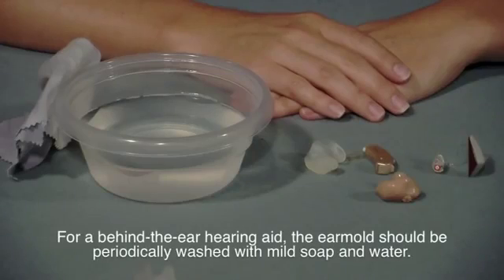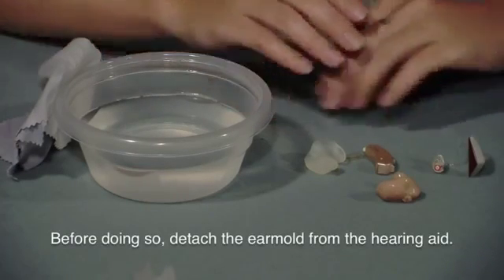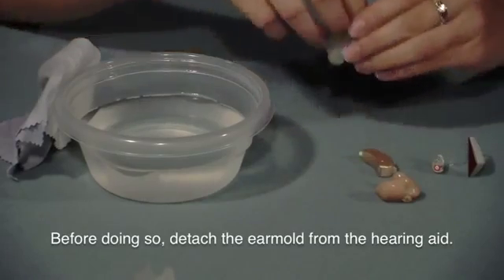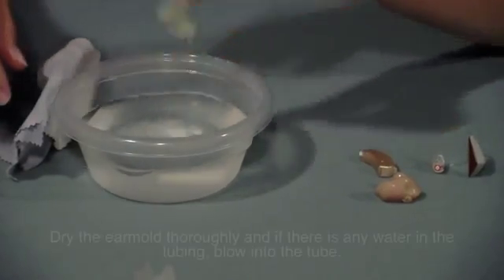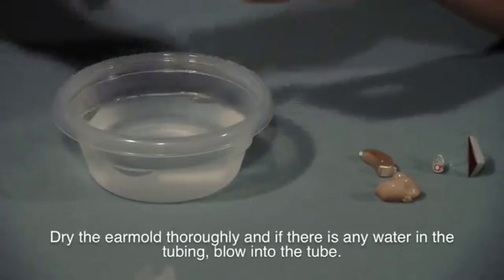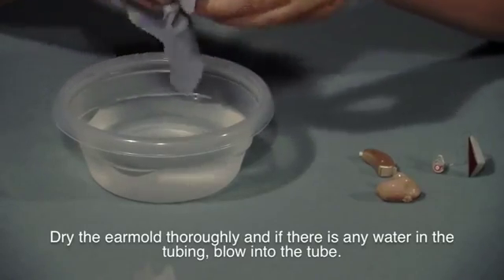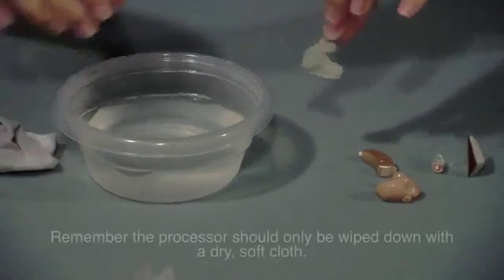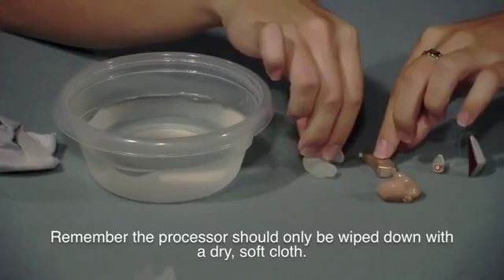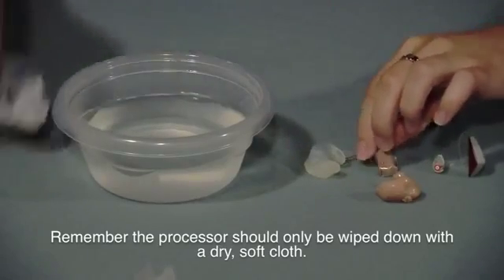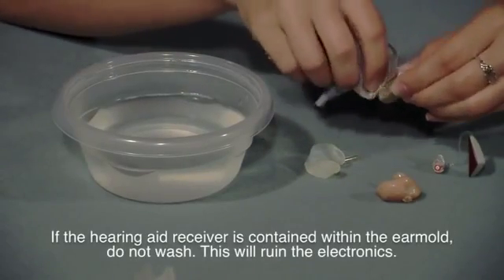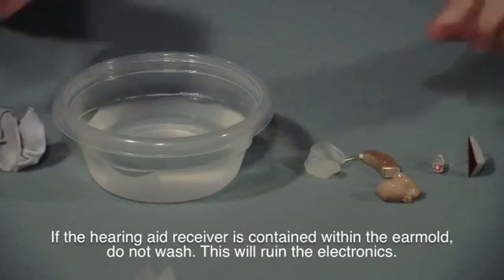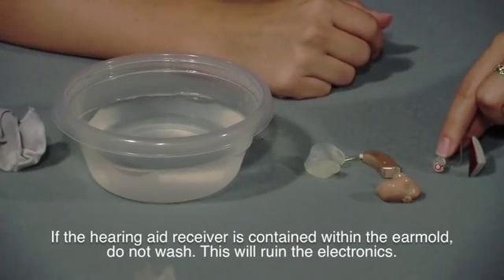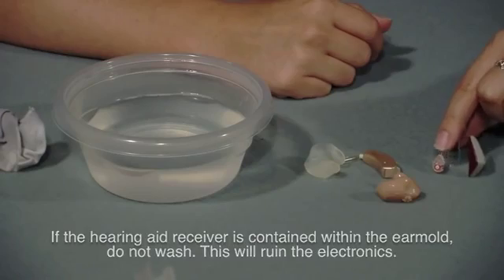For a behind-the-ear hearing aid, the ear mold should be periodically washed with mild soap and water. Before doing so, detach the ear mold from the hearing aid. Dry the ear mold thoroughly, and if there is any water in the tubing, blow into the tube. Remember, the processor should only be wiped down with a dry, soft cloth. If the hearing aid receiver is contained within the ear mold, do not wash. This will ruin the electronics.